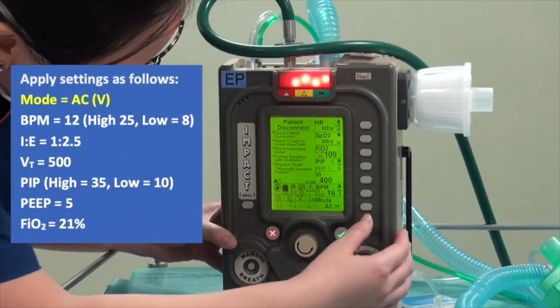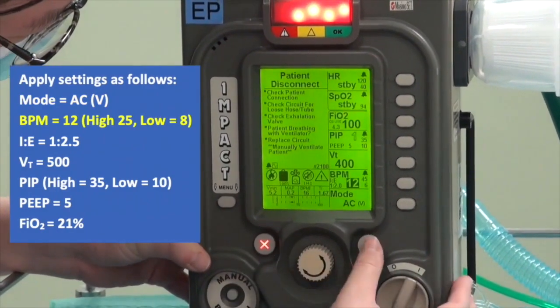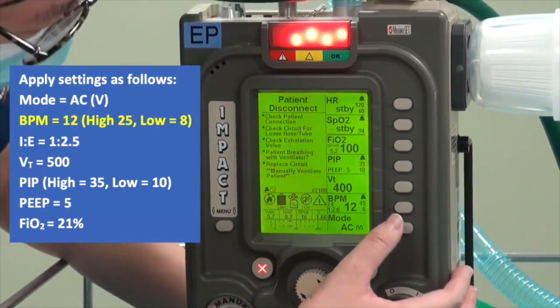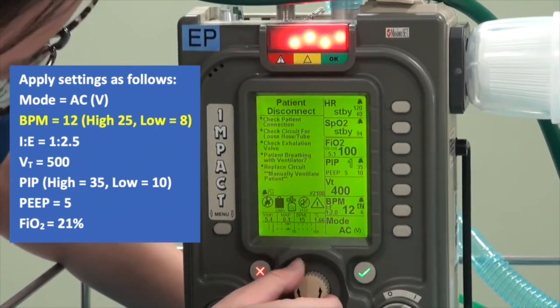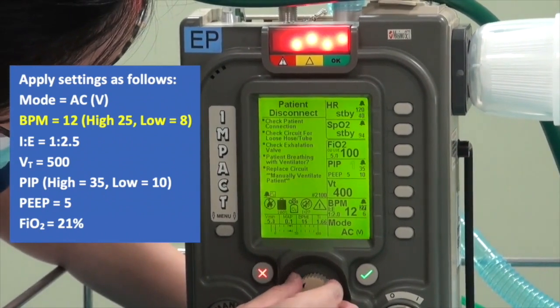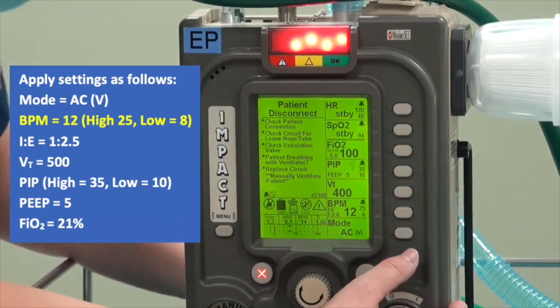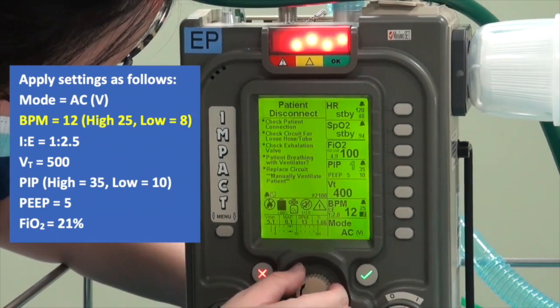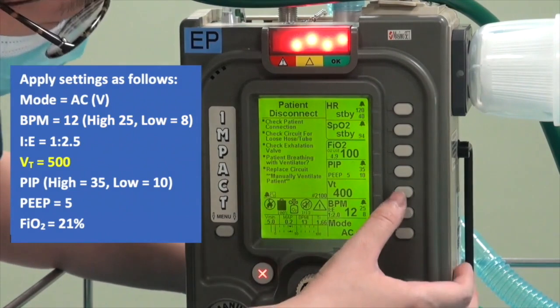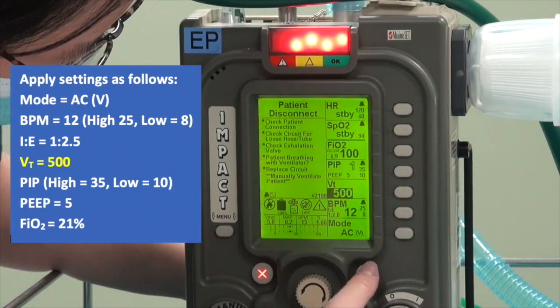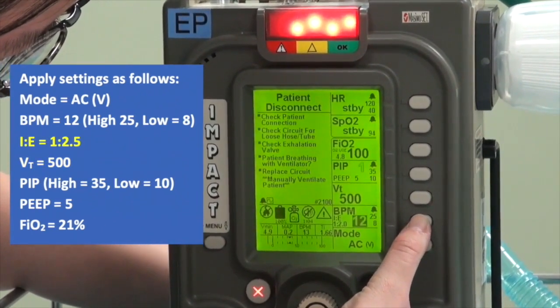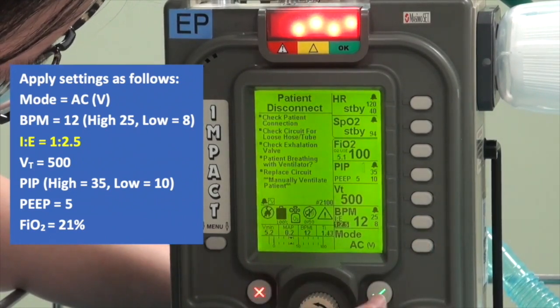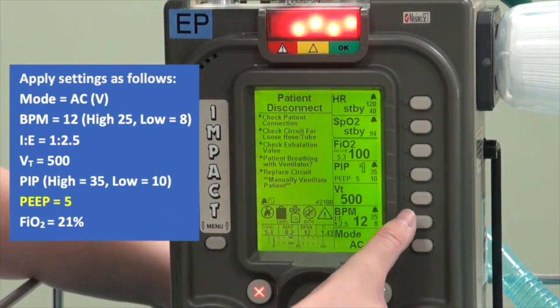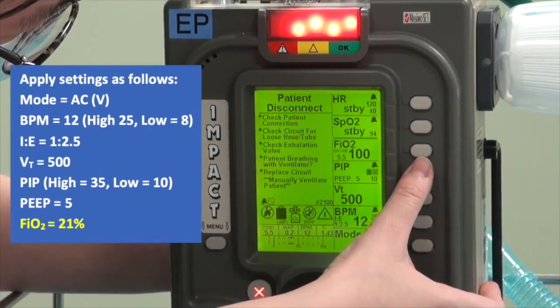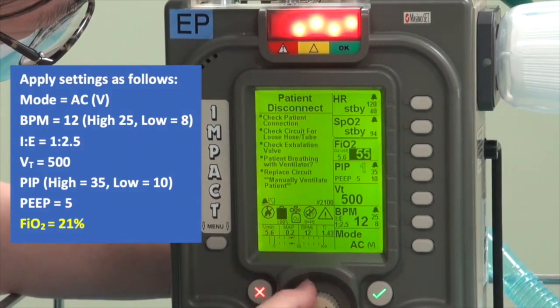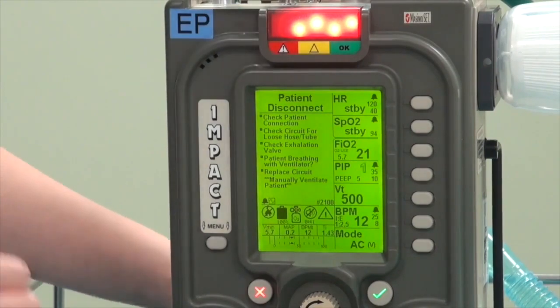I'll be setting a set breaths per minute of 12. My respiratory rate alarm limits will be 25 and 8. My set volume will be 500. I to E ratio of 1:2.5. PEEP of 5, and FiO2 of room air. Connect to a test lung.